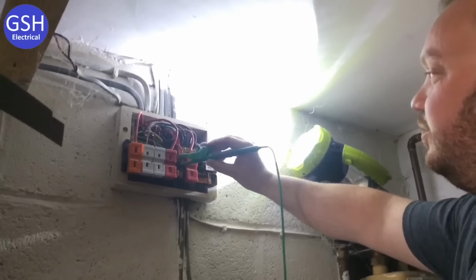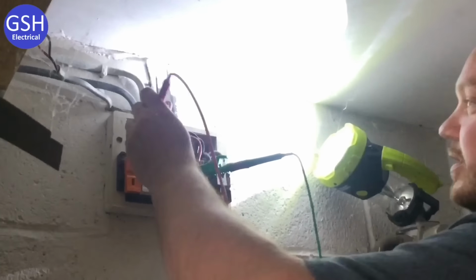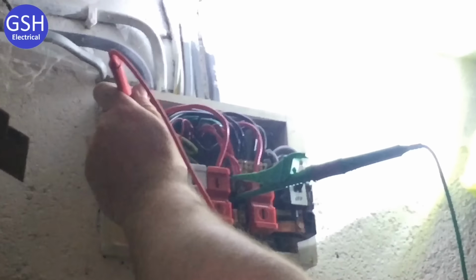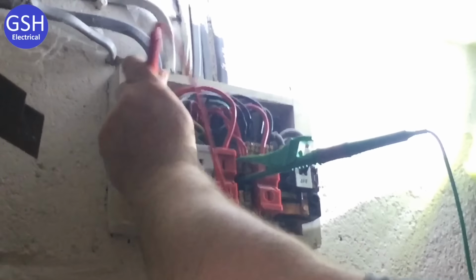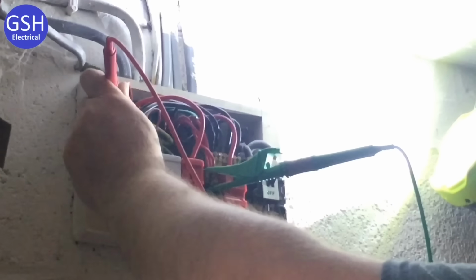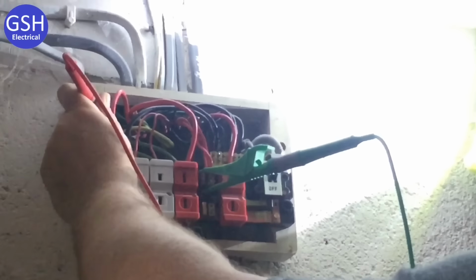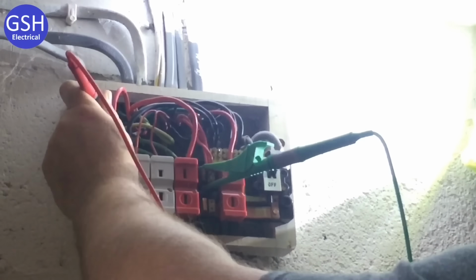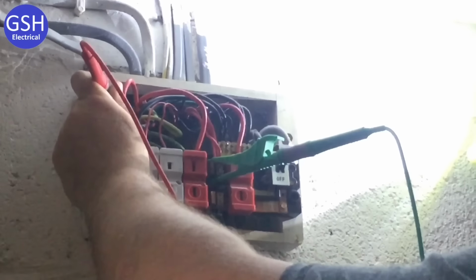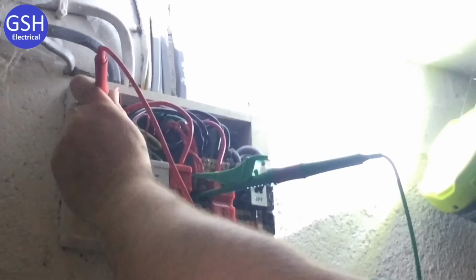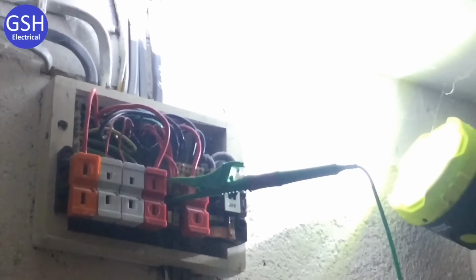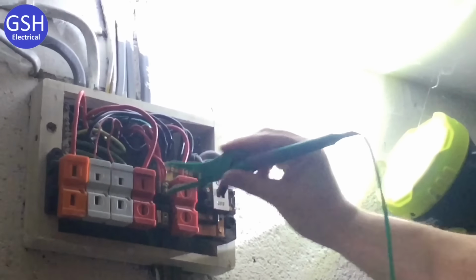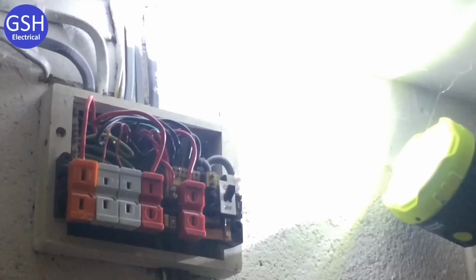Let's see you do that test. So I'm going to put the crocodile clip onto the line, and then I'm going to probe onto the CPC and hold down. What reading have you got? I've got 45. Okay, 45 mega ohms. And now you can test between? I'm going to test between the neutral and CPC.